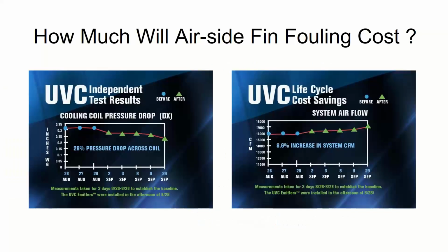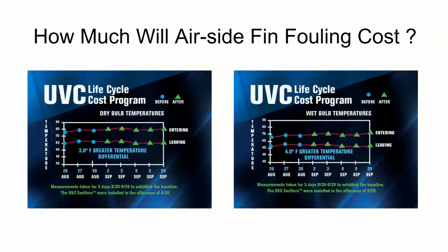Other things that we had talked about were pressure drop and airflow. By keeping the coil clean, you can reduce the pressure drop through the coil, thereby increasing the airflow if it's a constant volume system. If it's a VAV system, you won't increase the airflow because the VAV tracks the airflow, but you'll decrease the energy because the VFD will slow down to match that up.